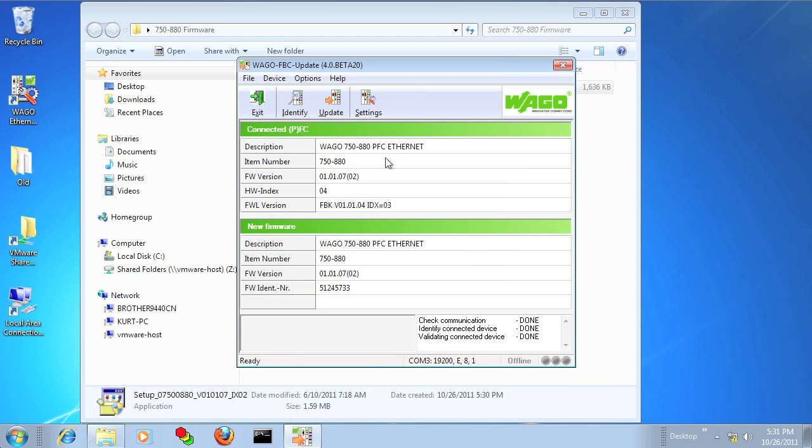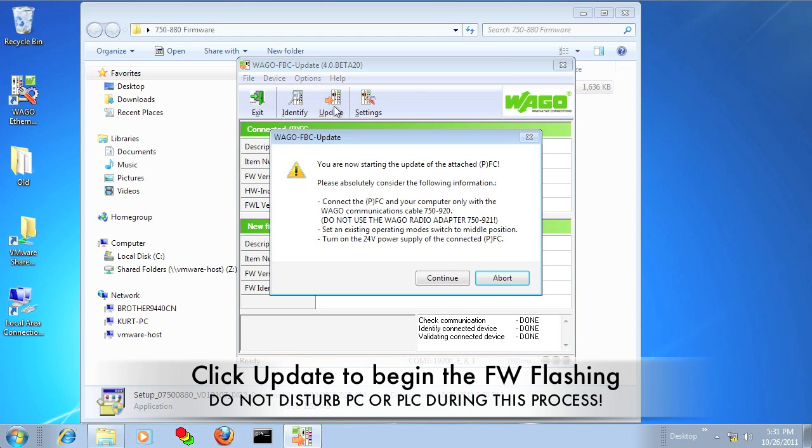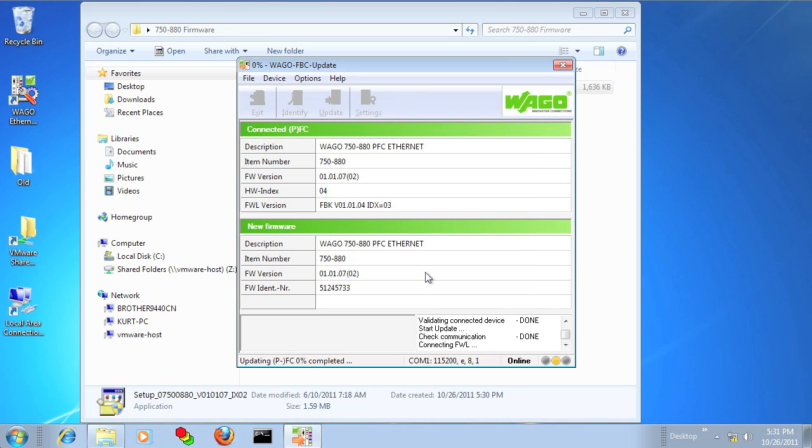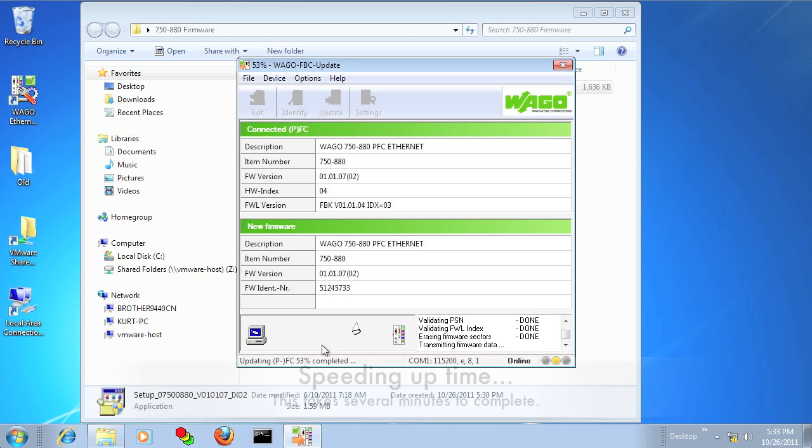After you've reviewed the new firmware and you're ready to update, go ahead and click the Update button and click Continue. The update process will take several minutes. I've accelerated the process here in the video, but you definitely do not want to interrupt the transfer of the firmware at any point, or you can permanently damage the PLC.